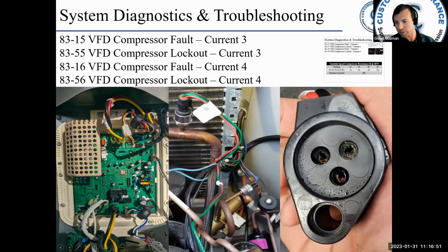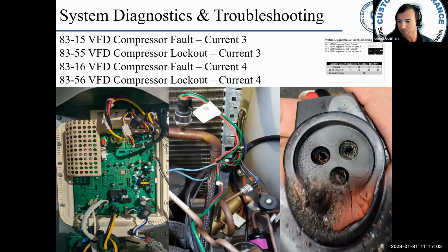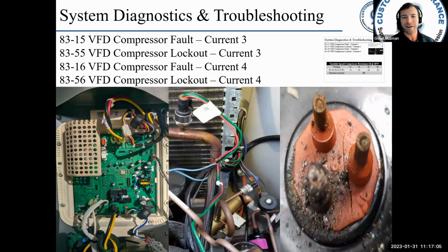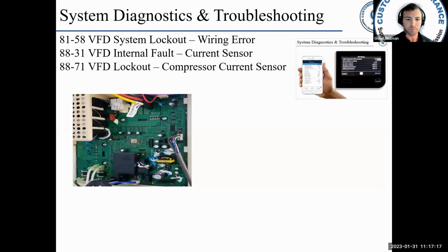Pull the plug off. In this case, I had a couple of these current 3 and current 4 faults, and I had the guy pull the plug off, and hey, look at that plug. Doesn't look very healthy. Took a look at the compressor terminals. There you go, there's a problem with that compressor. There was a poor connection that caused a high current draw, and eventually the terminal burned. So that's a compressor failure.